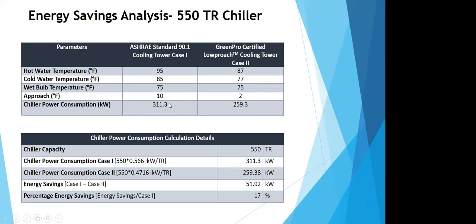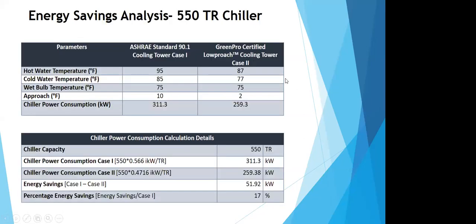Based on this, the consumption of a 550 ton chiller comes to around 311 kilowatts. Now, if we use a low approach cooling tower and aim to achieve, say, a 2 degree Fahrenheit approach, then the outlet water from the cooling tower would be 77 instead of 85, and the incoming hot water temperature to the cooling tower will be 87. The range remains the same. The range here is 10 degrees, and the range over here is also 10 degrees. But here the approach has come down from 10 to 2.